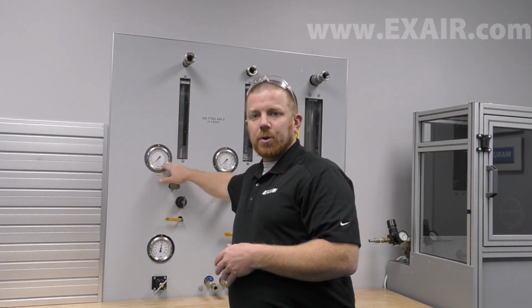This type of gauge can be calibrated, and when it's used in a critical application, such as an efficiency lab or another critical process, it should be. Here in the lab, we will actually use a calibrated analog gauge prior to the rotometer in order to get an accurate reading of what the pressure is that we need to correct for. Then we'll place another calibrated gauge just before the inlet of the device we are testing in order to get the accurate operating pressure of that test.